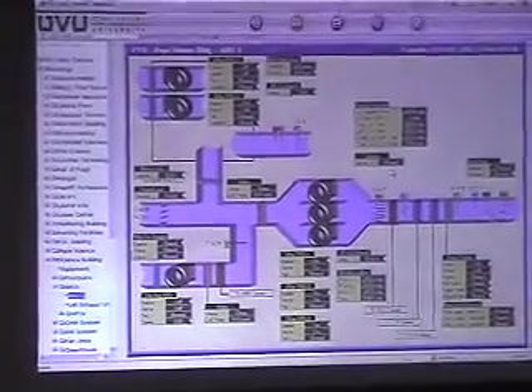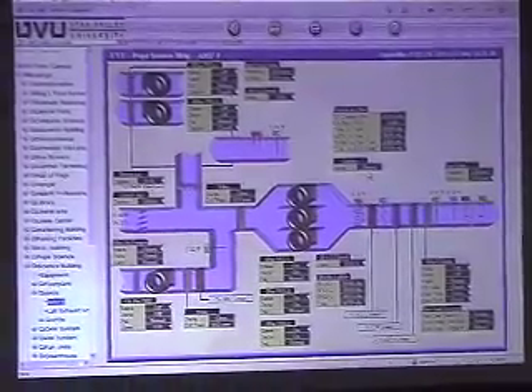Any questions on the air handler? On the safeties, what are all the safeties on that air handler? So you've got your high duct static, your freeze stat, and a fire alarm. That's it. That's the safety loop. You'll show us the free stats? Yeah. And these free stats are auto reset. Because of how big they are and where they're located, they're actually up on top of the air handler and they just come straight down because of the size of it. So it saves you from having to get a 20-foot ladder out to get up there to reset them.